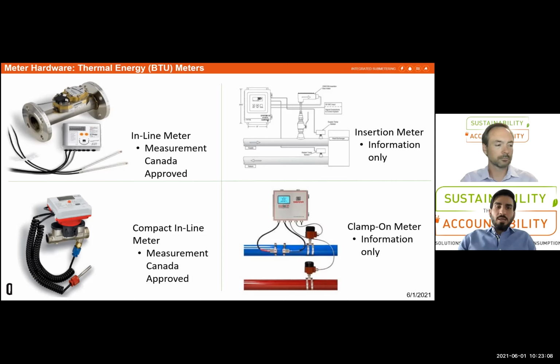And then clamp-on meters, which are suitable for temporary installations and energy audits or validation of other types of meters, offering lower accuracy due to additional uncertainties such as pipe thickness and so on. But advantageous in the sense that they could be installed seamlessly on the outer surface of the pipes. Next slide, please.